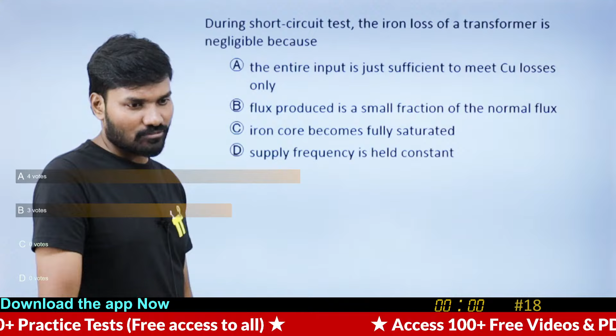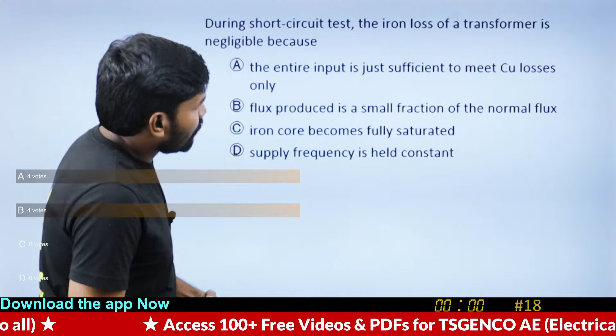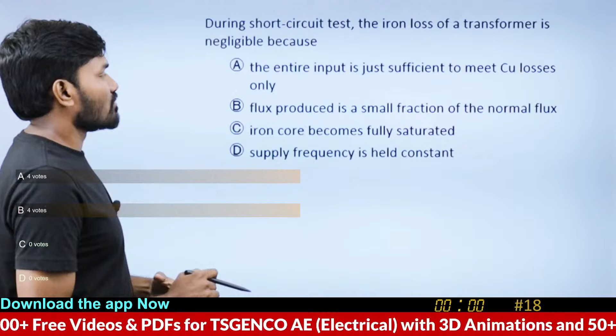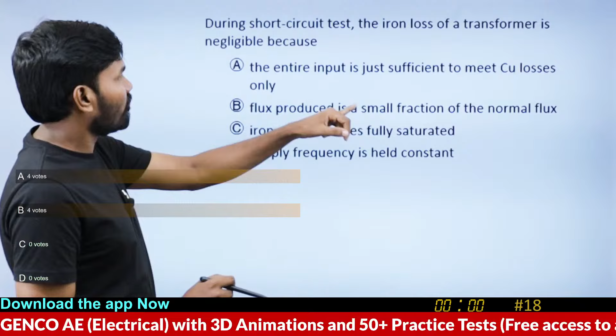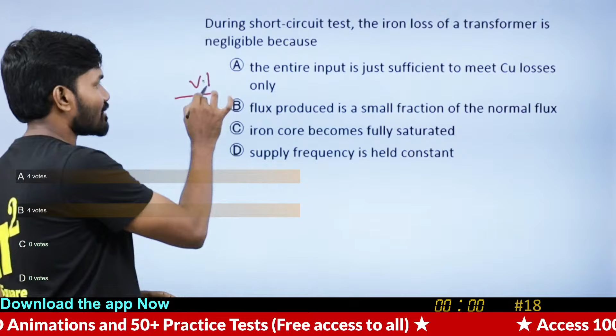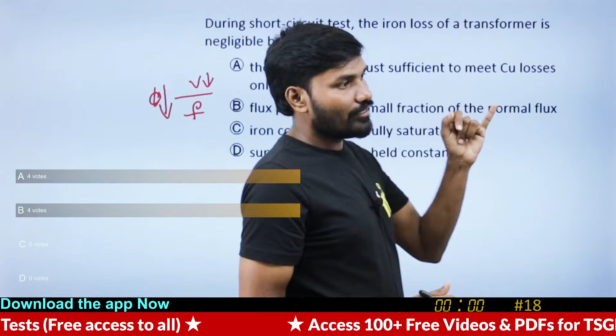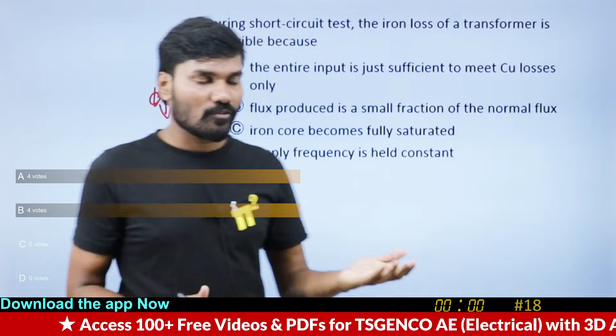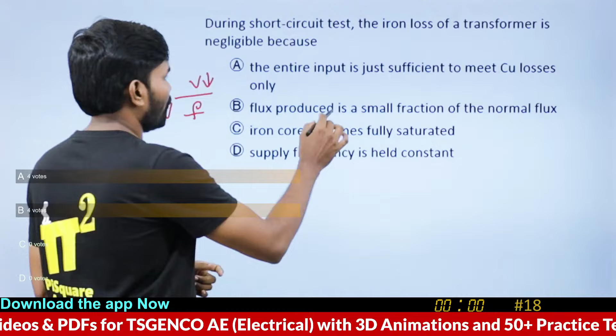How come you got mixed answers for this too? Let me see the question. Time's up by the way. During the short circuit test, the iron losses of a transformer are negligible because the flux produced is a small fraction of the normal flux. You're giving the same rated frequency, but the input voltage is less, so the flux is less. If the flux itself is less, the eddy current and hysteresis losses, which depend on flux, will also be less. So iron losses will be less because the flux produced is small. It's 50-50, which isn't quite expected for this question.